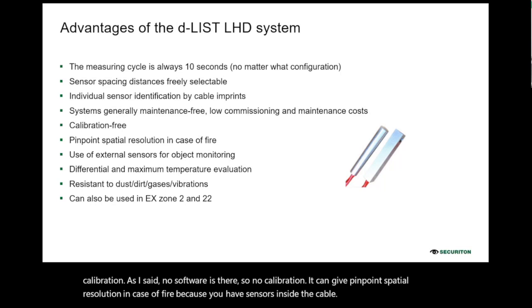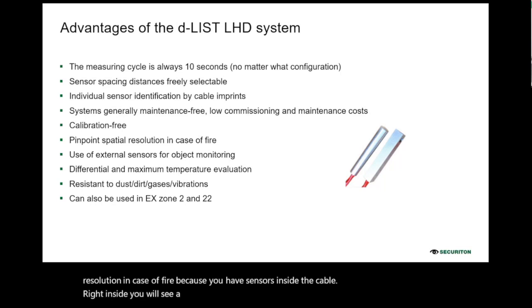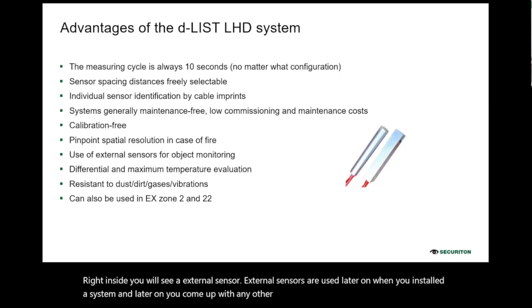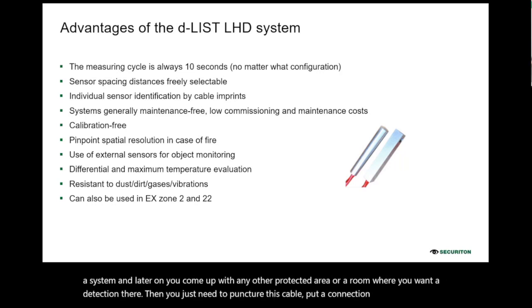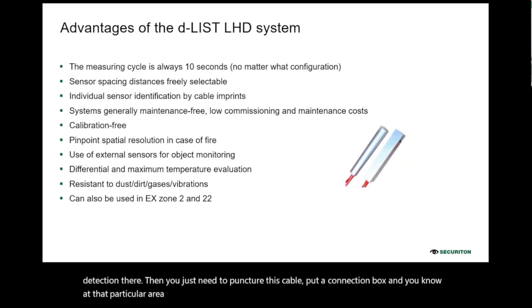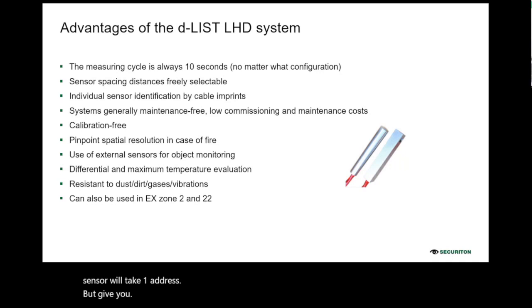On the right-hand side, you will see an external sensor. External sensors are used later on, when you have installed a system and then come up with another protected area or a room where you want detection. Then you just need to puncture this cable, put in a connection box, and at that particular area where you want detection, you just drop in this external sensor. This sensor will take one address but give you heat information. Differential and maximum temperature evaluation is possible, or a combination, and individual evaluation is also possible.